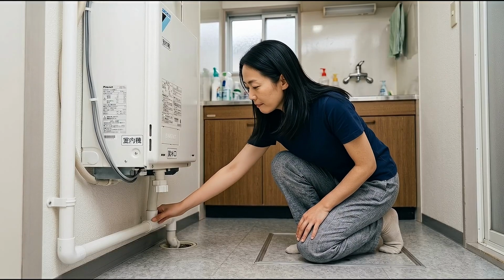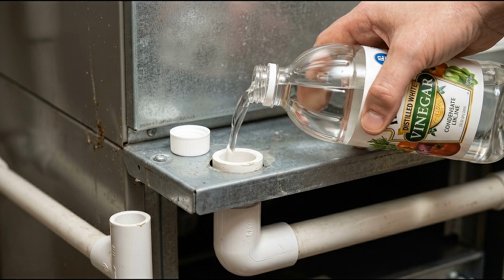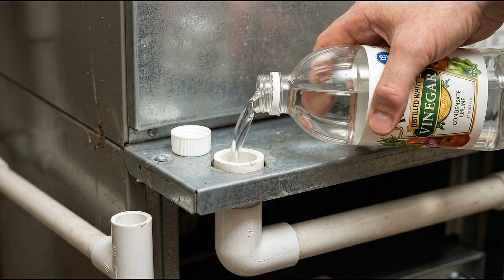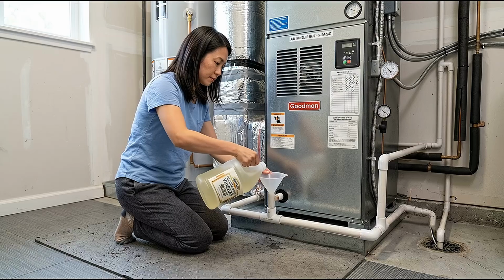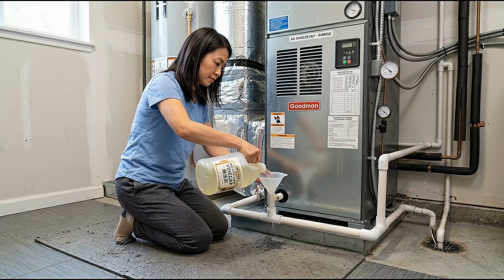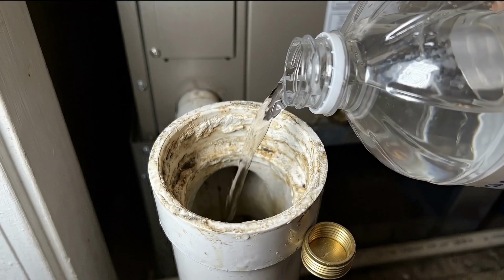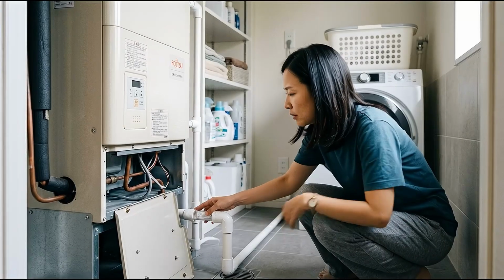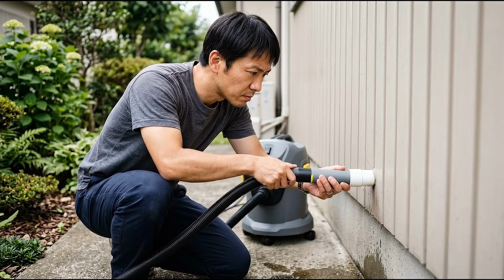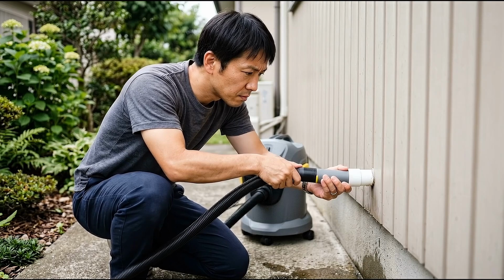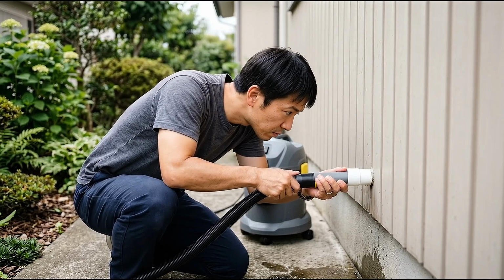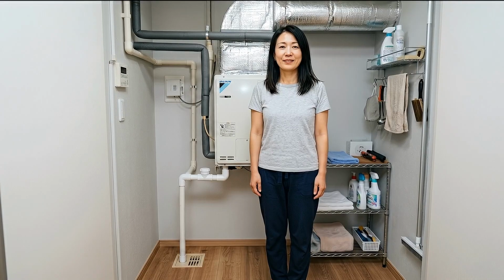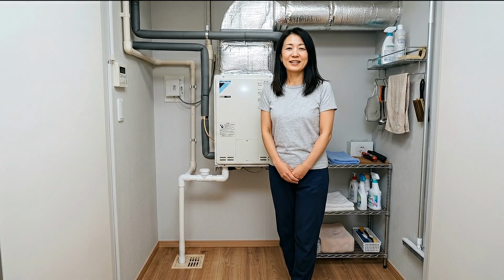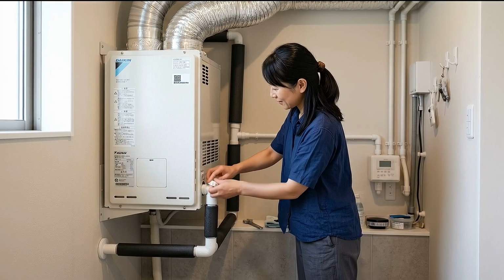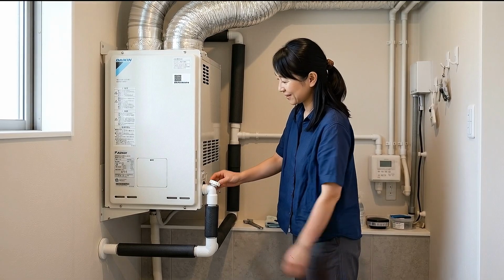Clearing the line is simple. Pour a cup of distilled white vinegar into the drain pan or the access point on the drain line once a month during cooling season. The vinegar kills the algae and dissolves the buildup. If the line is already clogged, a wet-dry vacuum applied to the outdoor end of the drain pipe will usually pull the blockage out. This is a 2-minute job that prevents a potential water damage claim on your homeowner's insurance and a $200 service call.